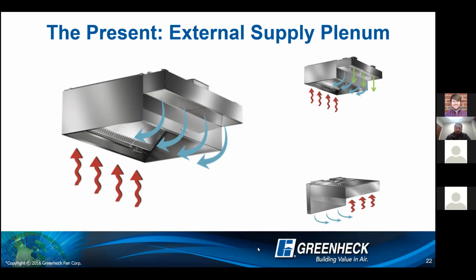Back supply plenums are commonly used when you have untempered makeup air. So if you have truly untempered makeup air, you would utilize a back supply plenum so that you're not dumping all that untempered makeup air on the cook's head from this ASP. You're going to bring in a significant portion of your outside air through this back supply plenum, which is a 6-inch wide plenum mounted to the wall that cuts off 32 inches from the floor. And then the air is returned in at the 32 inches above the floor.